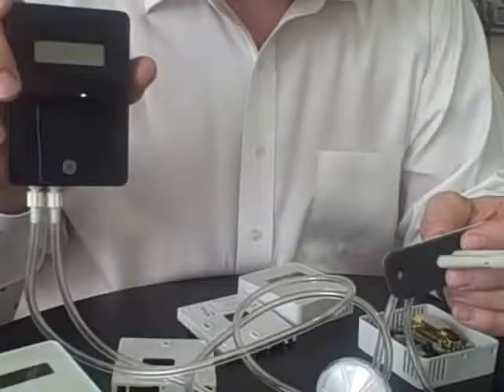Moving on, the only other option we want to talk about today is our duct-mount version. This comes in black — in fact, you can order any of these products in black. It's a UL 94V-0 enclosure, as these all are in terms of fire resistance. You mount this on the side of the duct and use these pitot tubes here, connected to the bottom of the instrument, to get a duct CO2 measurement.